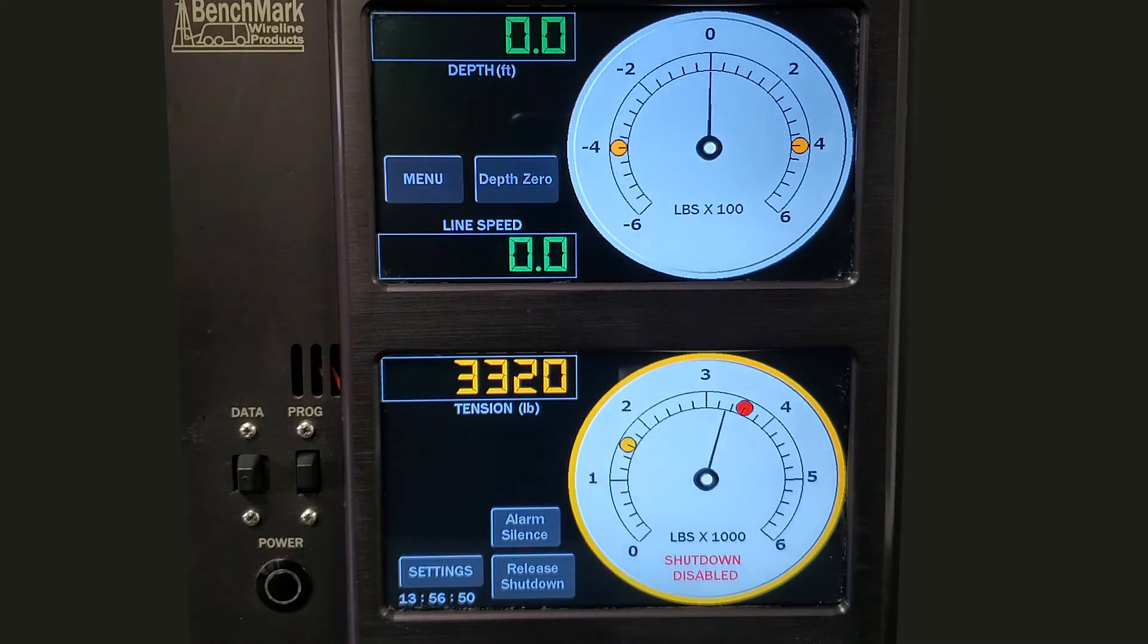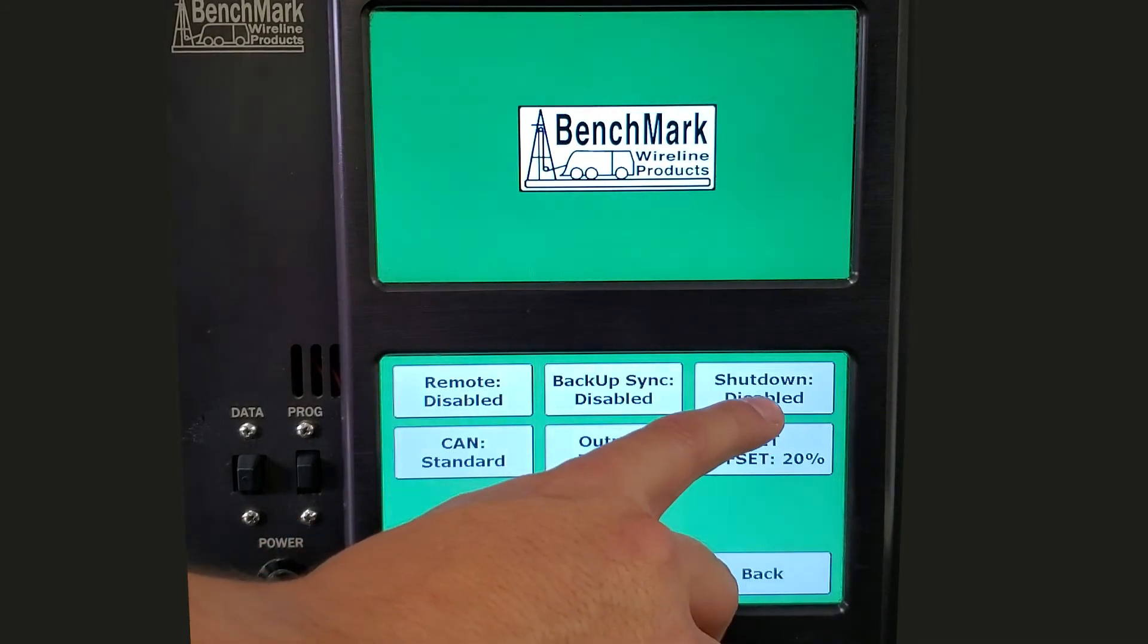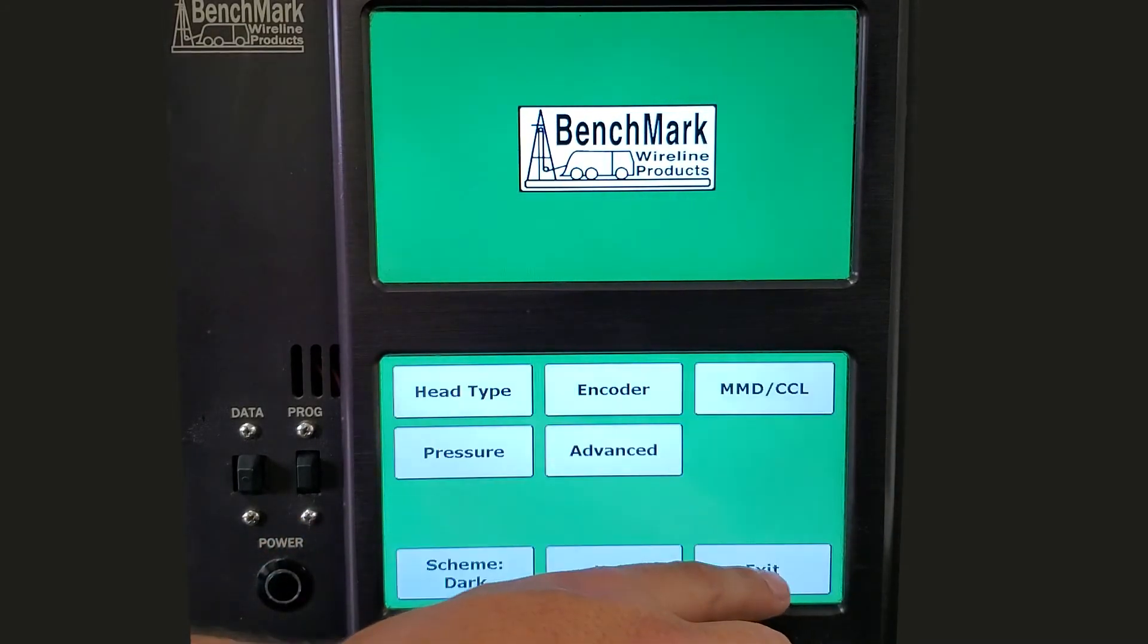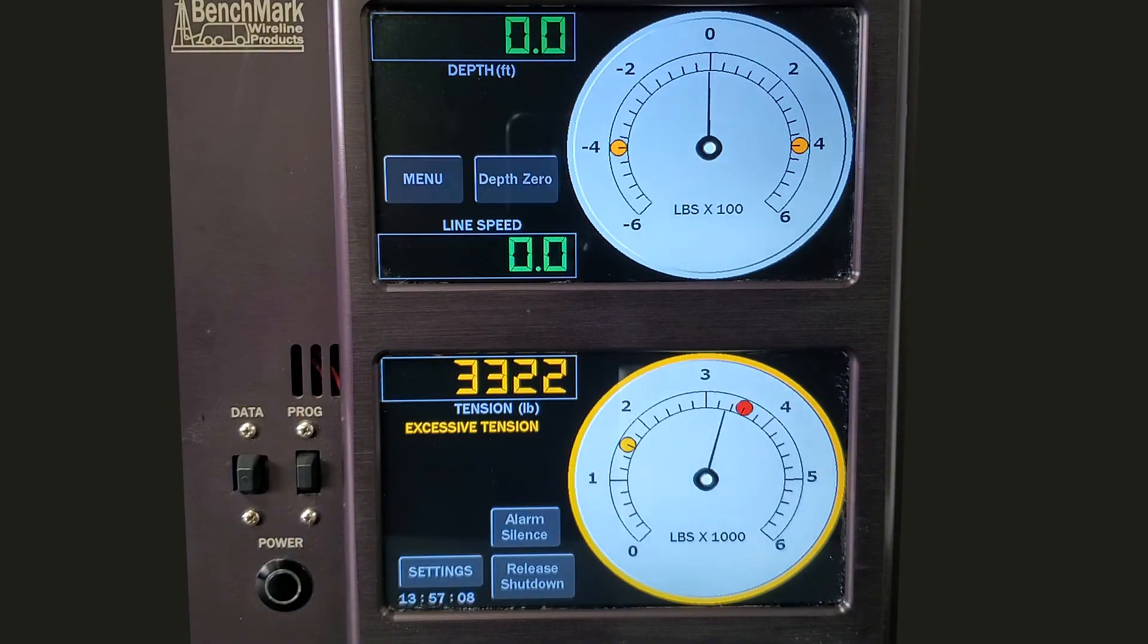After the line is free, be sure to promptly turn off the Shutdown Disabled command, which will restore the shutdown safety system. To do that, click Settings, Advanced, Shutdown Disabled, which re-enables the shutdown safety system, then Back and Exit. The shutdown disable message will be gone and the system will be restored.